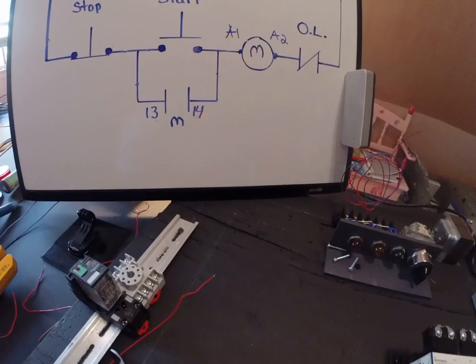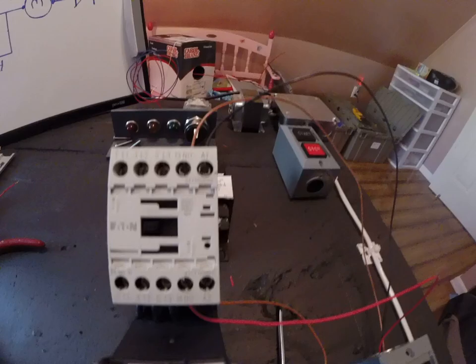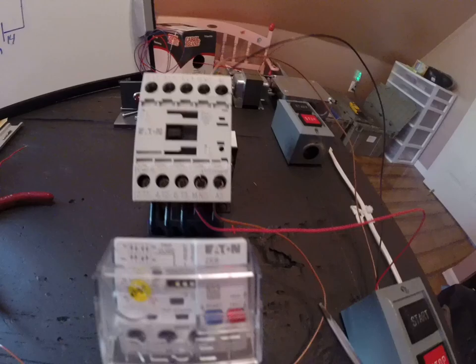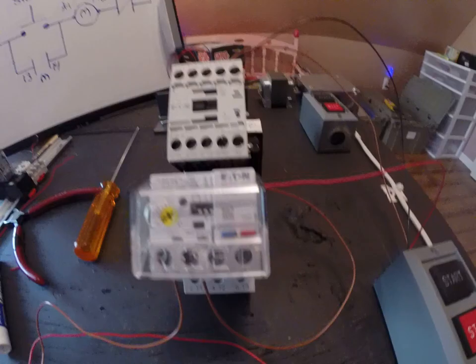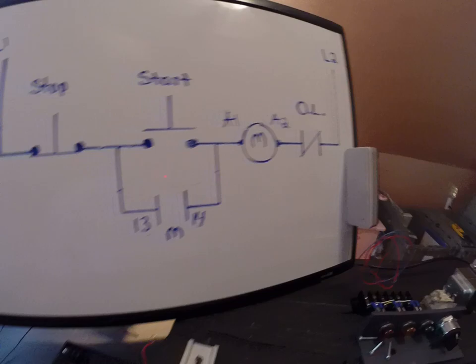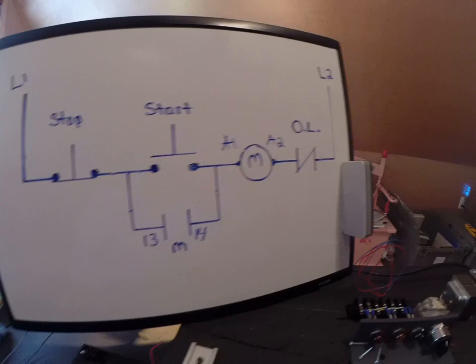So I opened up the device and found my normally open contact that most motor starters provide, and it allows me to be able to hold that circuit in as a latching or holding circuit when I energize it. So all we did was we took the new numbers from the new motor starter, translated them to our simple stop-start circuit.